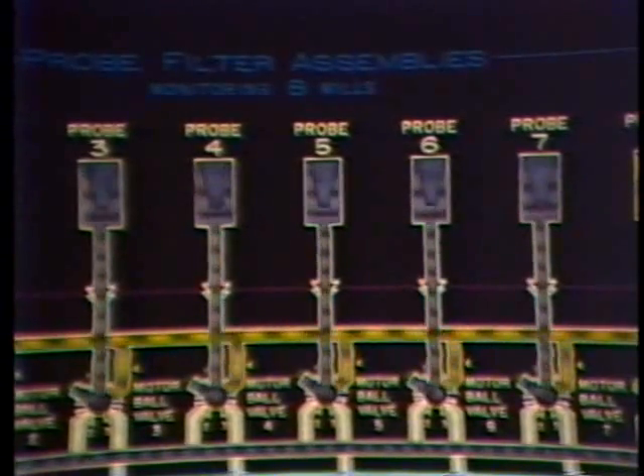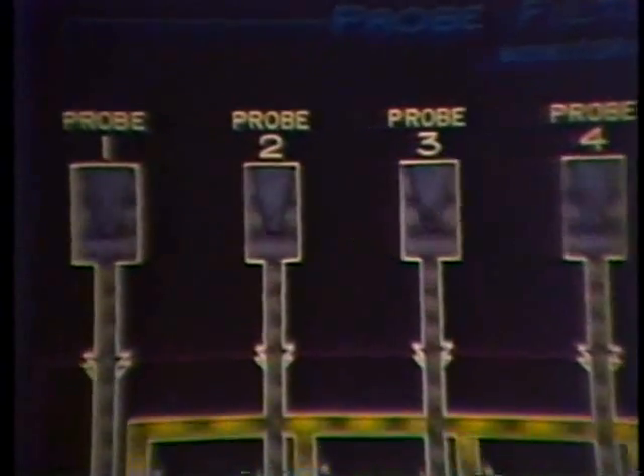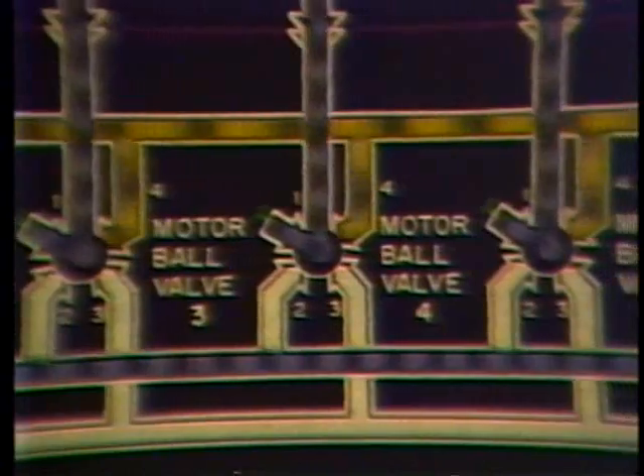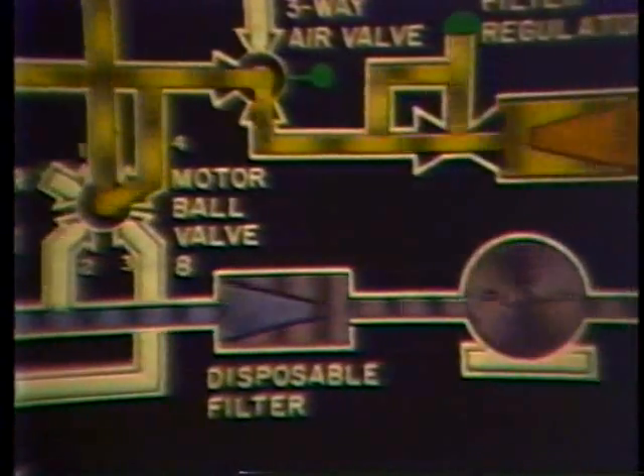The computer is programmed to control the sampling selector valves for 1 to 12 hazardous locations. The microprocessor stops the sample gas flow from all probes except the one being analyzed and the one next in line. To assure immediate response time and a fresh sample, the sample gas flow from the probe next in line is vented overboard in preparation for analysis. This technique assures that a fresh sample from each location is always available for analysis, and it reduces lag and transit time to a minimum.